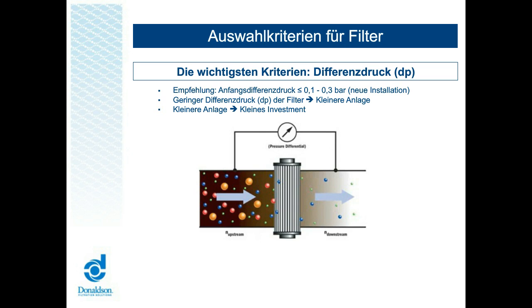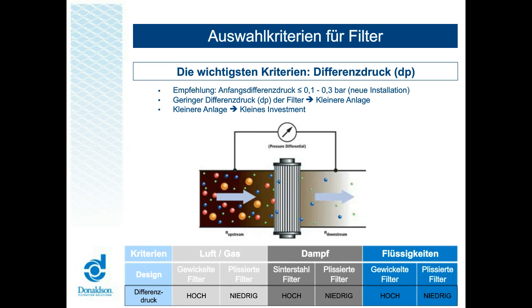Für neue Anwendungen empfehlen wir einen Bereich von 0,1 bis 0,3 Bar als Anfangsdifferenzdruck. Die Bestrebungen, den Druckverlust so gering wie möglich zu halten, sind unmittelbar mit den Kosten des Systems verbunden. Bei gegebenen Druckverlustanforderungen können die Filtersysteme kleiner ausgelegt werden, was sich günstig auf den Investitionsbetrag auswirkt. Als Daumenregel gilt, dass plissierte Filter geringere Druckverluste aufweisen als gewickelte, schmelzgeblasene oder gesinterte Pendants — und zwar unabhängig vom Fluid selbst.